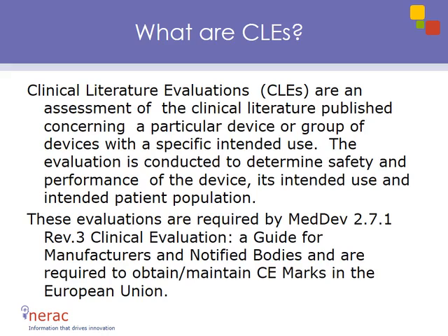These evaluations are required by MedDev 2.7.1 Rev 3 and are required to obtain and maintain CE marks in the European Union. The clinical literature evaluation is a subsection of the larger clinical evaluation report.